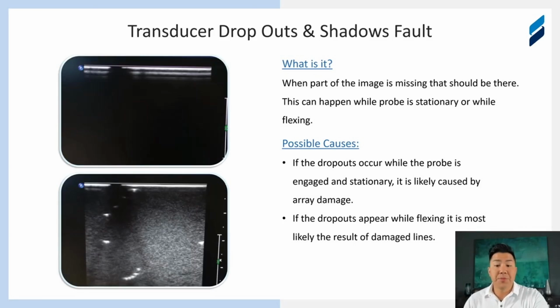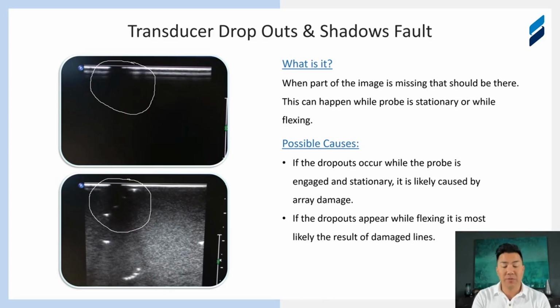Here, again, we've seen this before, dropouts on the transducer. We know it's a transducer, and here you can see in the air scan, we got this pretty large section of dropped elements, and if we scan a phantom, you're going to see that it's just missing all of this information. So again, if we were flexing the strain relief cord area and this goes in and out, so the information is correct and then it disappears on the image, you likely have some line issues. But if you can't do that and you can't induce that type of reaction from the transducer, you're looking at a connector or a crystal issue.